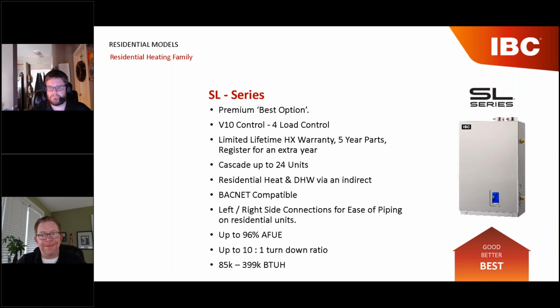This unit, because it's designed for much larger applications, can actually cascade up to 24 units. Again, like the VX, it has residential heat and domestic hot water with the use of an indirect. Chris talked about this earlier from a licensing standpoint. BACnet does come in these units. So when you're doing that McMansion with a big fancy control system, all you need to remember is to buy a BACnet license. The control guy will do the rest. The other thing about the SL, which in my opinion is fantastic, is it has left and right side connections.